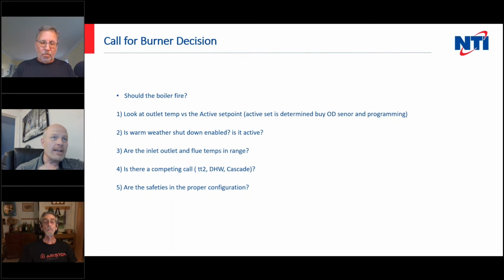Every boiler ever made goes through a decision before it decides to fire the burner. So the first thing the boiler has to do is decide, should it do anything? You've asked it for heat via your jumper wire for thermostat or jumper wire for hot water or tank sensor or aquastat, whatever it is you're using. So the boiler is then going to look at its outlet temperature versus the active set point. And keep in mind, guys, especially with these newer boilers, you can only have 1 active set point, but you could have 4 or 5 total set points.